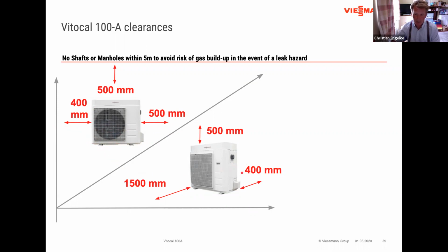Clearances to the back of the machine, that's where the air comes in, so the minimum is around 400 millimeters. If it's maybe a bit less, not so critical, please just make sure that the air is freely able to enter the back of the machine, because the fan is pulling the air into the machine. Any obstructions there, even window sills obscuring the airflow, will make it difficult, and the machine will then not be able to get all the air through the evaporator, and therefore loses performance.